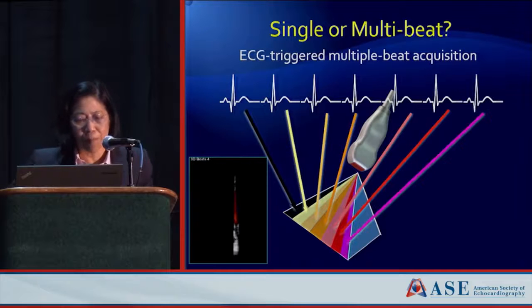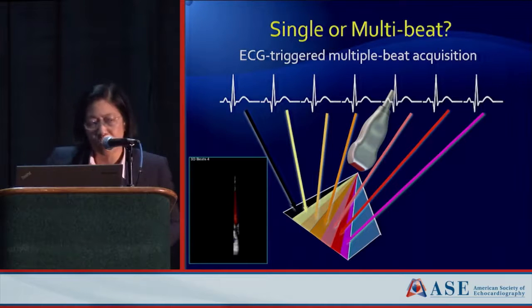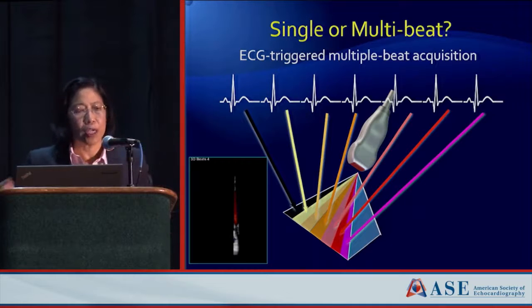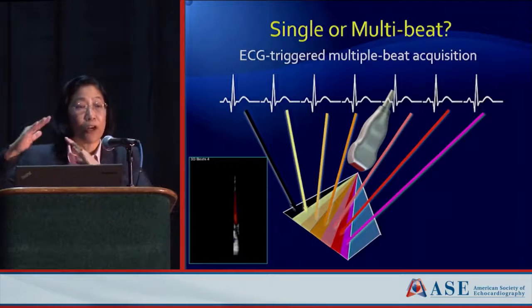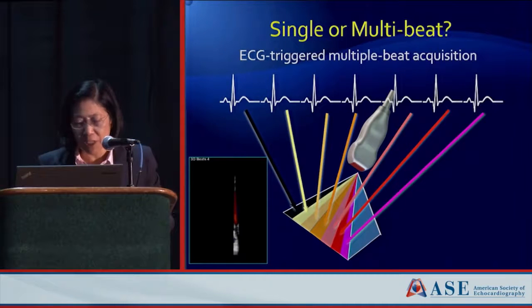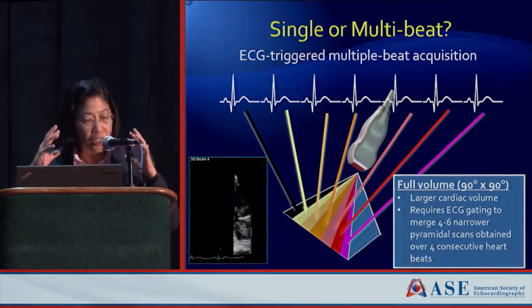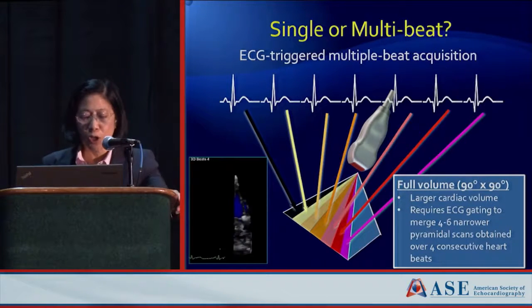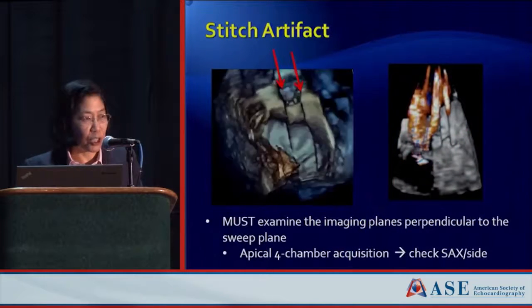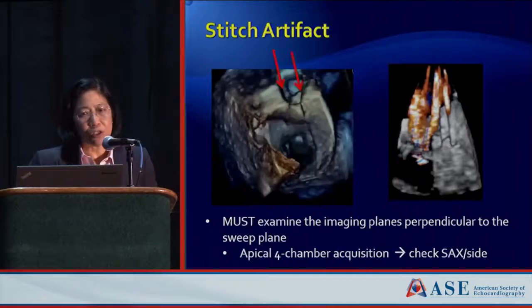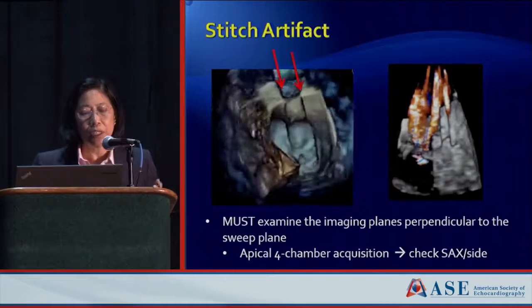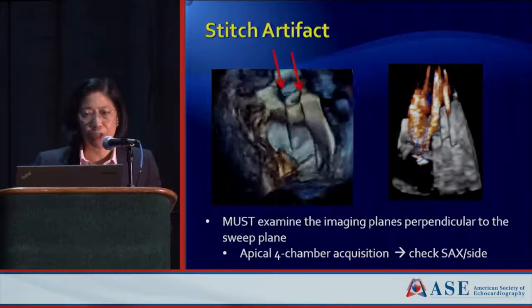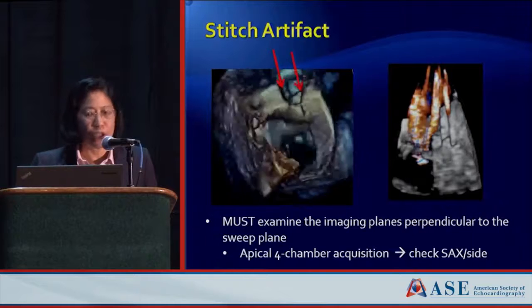One challenge we've had to live with is relatively low volume rates — the 3D equivalent of frame rate. The way we've gotten around this is to take very small volumes and splice them together. Multiple beats spliced together allow you to get a very large volume, but these are not a continuous real-time volume — they are composed of multiple small sub-volumes, and the major issue with that is the splice artifact.